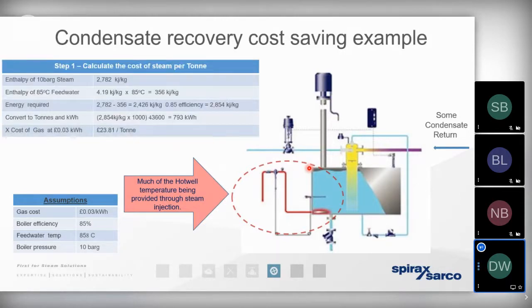So we can calculate the cost of the steam by, first of all, taking the energy that's present within the steam at the known pressure, 10 bar gauge, for example, and we minus the energy that is present within the water at 85 degrees. And if we then multiply that by the overall efficiency of the boiler, so by multiplying it by 0.85, we're then able to determine how much gas we then need to consume to raise the steam. And we then multiply that by the cost of the gas. And you can see that that gives us a cost of steam of £23.81 per tonne.